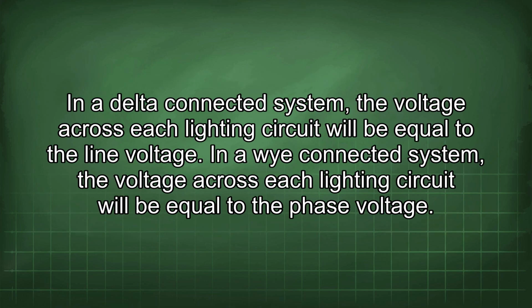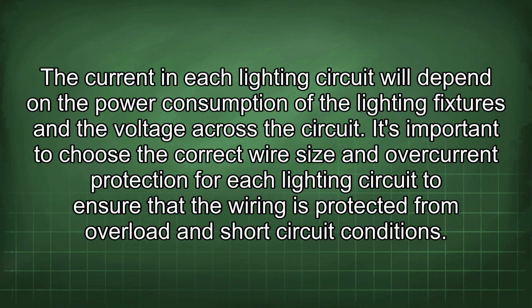In a delta-connected system, the voltage across each lighting circuit will be equal to the line voltage. In a Y-connected system, the voltage across each lighting circuit will be equal to the phase voltage. The current in each lighting circuit will depend on the power consumption of the lighting fixtures and the voltage across the circuit. It's important to choose the correct wire size and overcurrent protection for each lighting circuit to ensure that the wiring is protected from overload and short-circuit conditions.